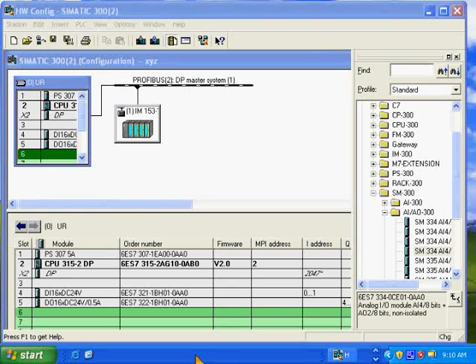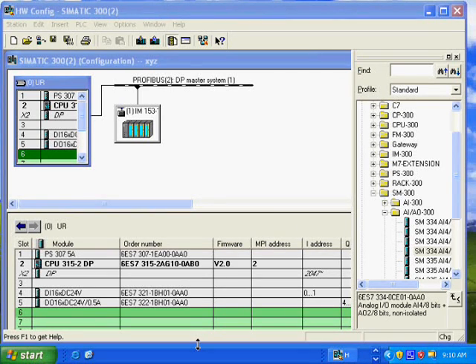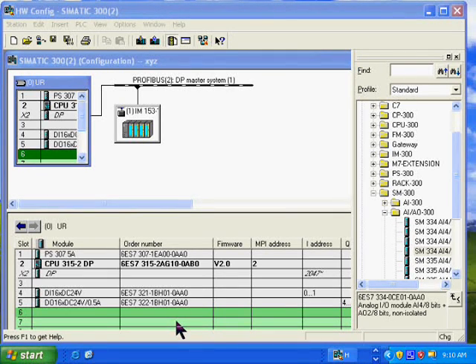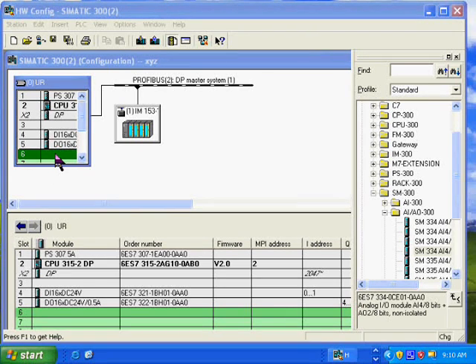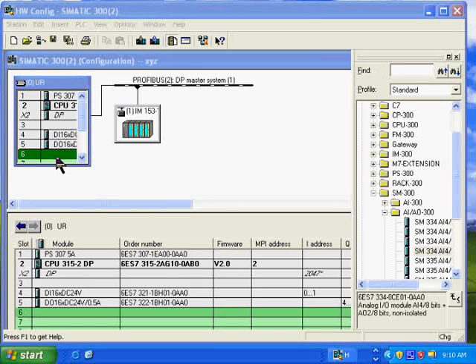Now we're looking at the hardware configuration tool, which is where we have to tell the system what slot contains what modules and then download that hardware configuration to the CPU. I left slot 6 empty to show you how easy it is to not only put a module in the proper slot, but also to configure the properties of that module.